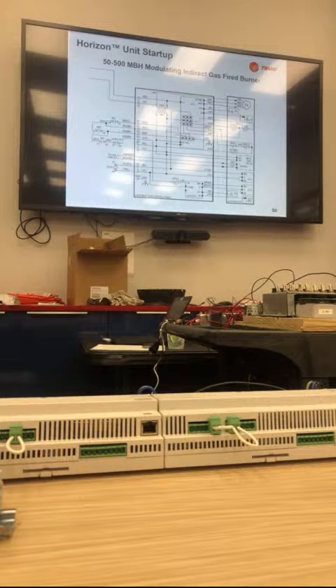That's why we came up with that third generation flue extension. If you're worried about combustibles of that nature, we do the flue extension to get it above the roof of the unit itself. We've also done that if they put the combustion exhaust here and an inlet of another unit here, we do the same thing. That's our recommendation. There's no other option for that. But the third generation flue, we still use that one. We know it works. Malinky, right? Is that the name? That was propane. That was the rough one.